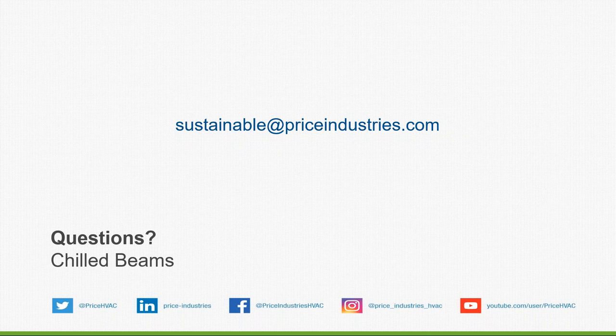Great. Next one is from AJ. What documentation do AHJs generally require to prove that the induction is consistently above ASHRAE 170 minimums? So we publish our induction ratios, and you can see that in the selection software. That's part of the ASHRAE 200 method of testing, so we do test for that. The way we get that reading is we use a grid of airflow velocity readings across the water coil. We'll take it on an inch by inch grid, and that's how we measure the induction ratio of the chilled beams. We don't test that in the field, but it is a characteristic we do test for in our lab before publishing our test data.